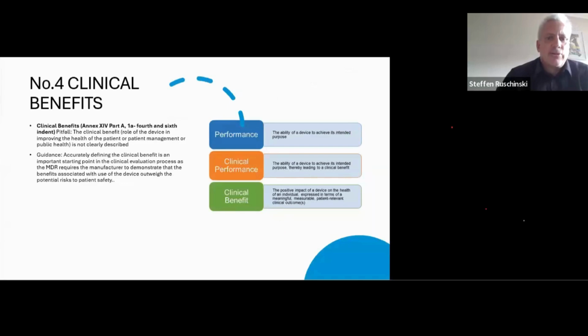The clinical benefit, so this is the role of the device in improving the health of the patient or patient management or public health, is not clearly described. Accurately defining the clinical benefit is an important starting point in the clinical evaluation process, as the MDR requires the manufacturer to demonstrate that the benefits associated with use of the device outweigh the potential risks to patient safety. When defining these clinical benefits, the manufacturer should consider the role of the device in diagnosis, monitoring, prevention, treatment, alleviation, etc. of a disease, injury, or disability, and the subsequent positive impact. If we have software devices, the role of the software in the overall clinical workflow should be carefully considered, dependent on the clinical performance of the device. The clinical benefit may be direct or indirect.